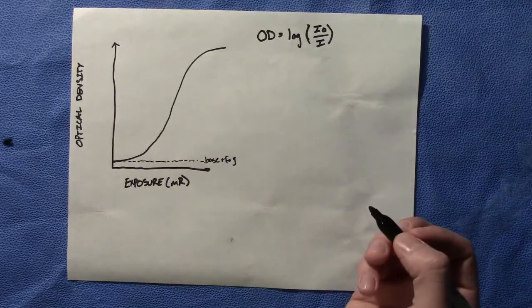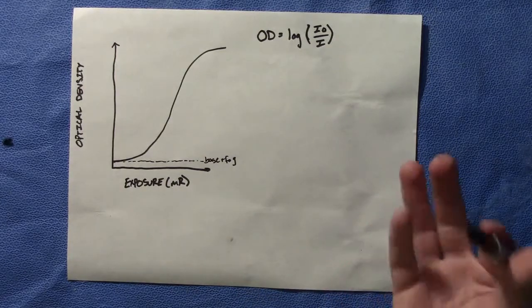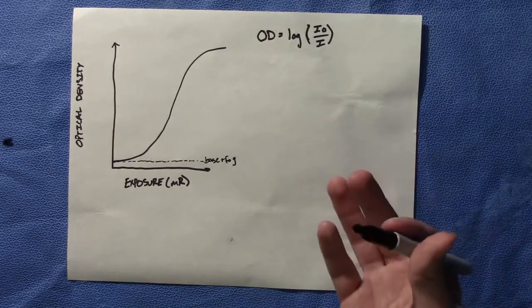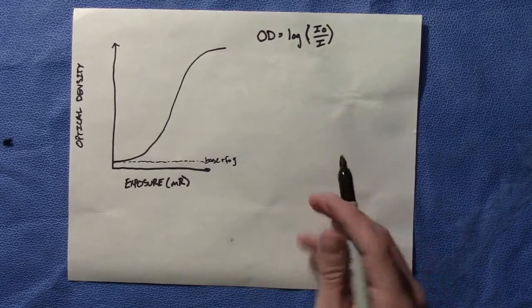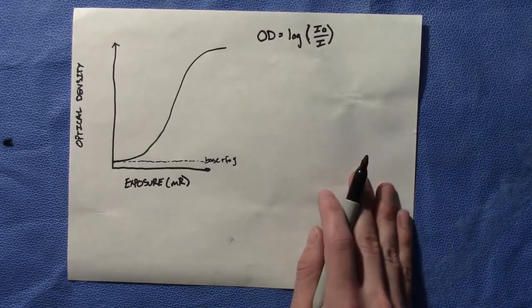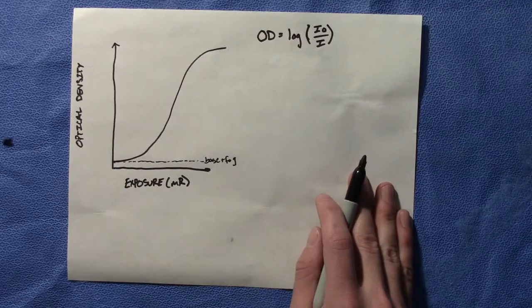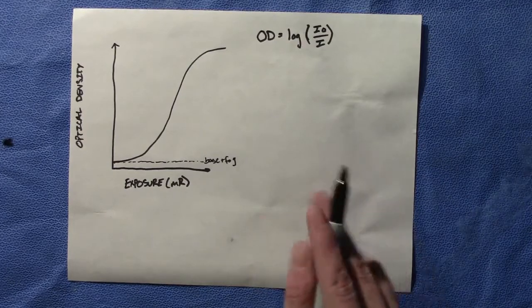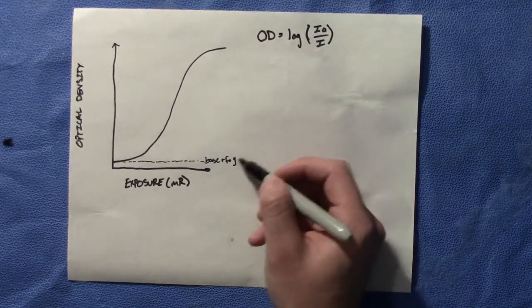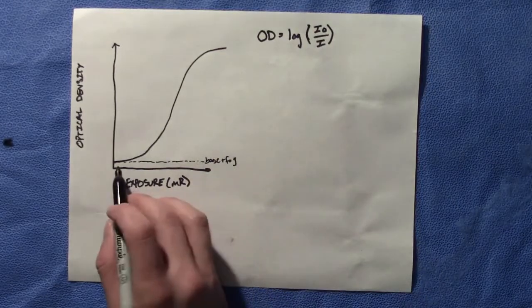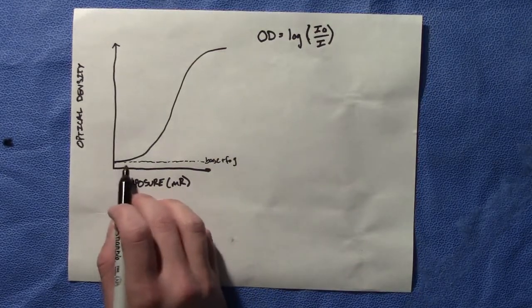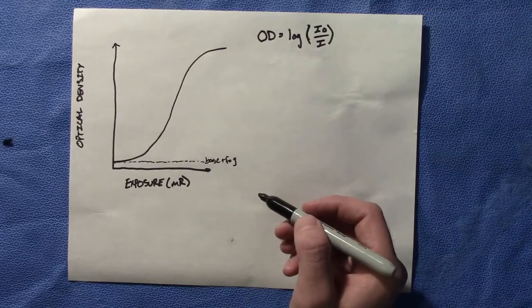Another thing: what's the speed of the film? The speed is simply the amount of radiation required to get an optical density of one above this base and fog. It doesn't include base and fog because we immediately have some type of inherent optical density.